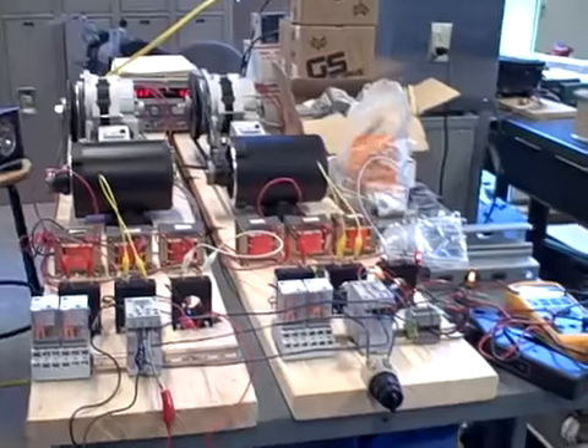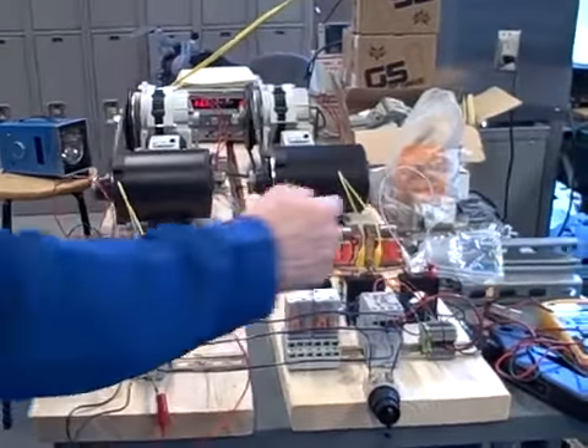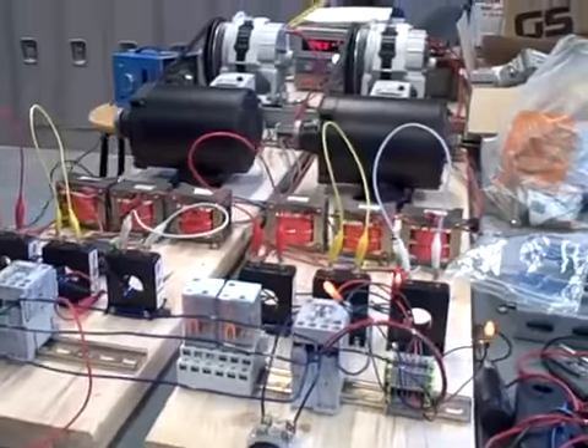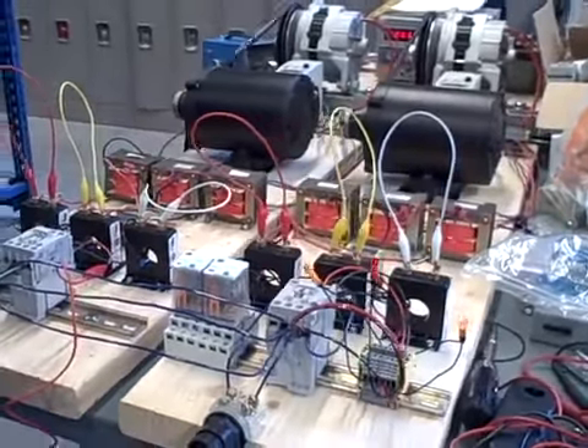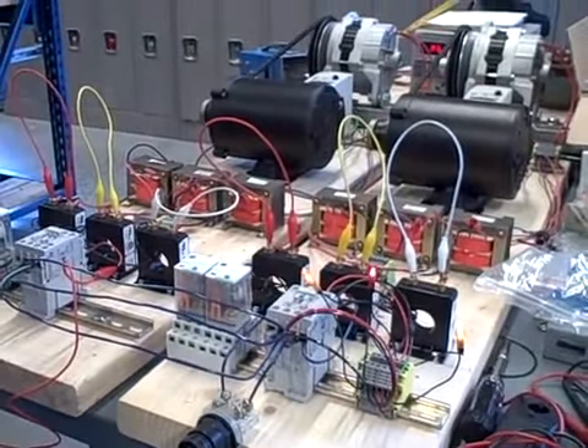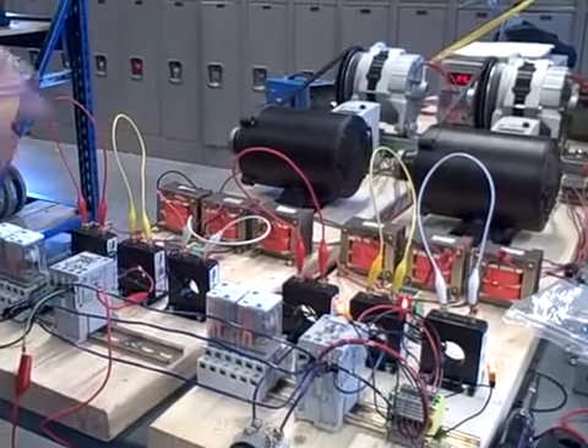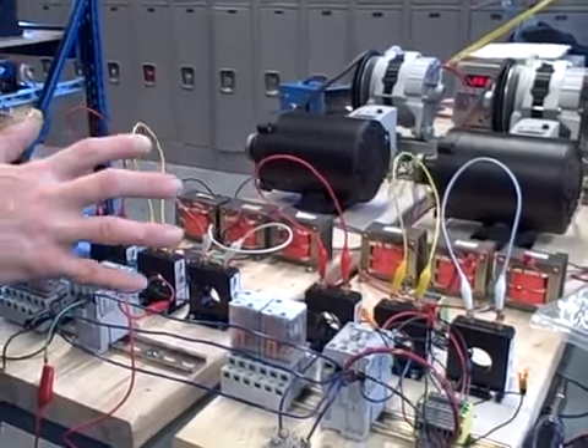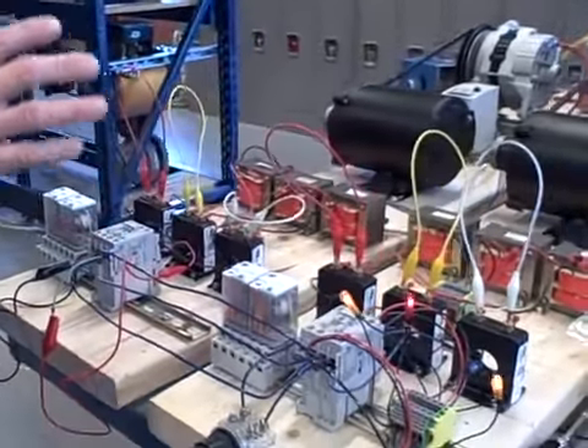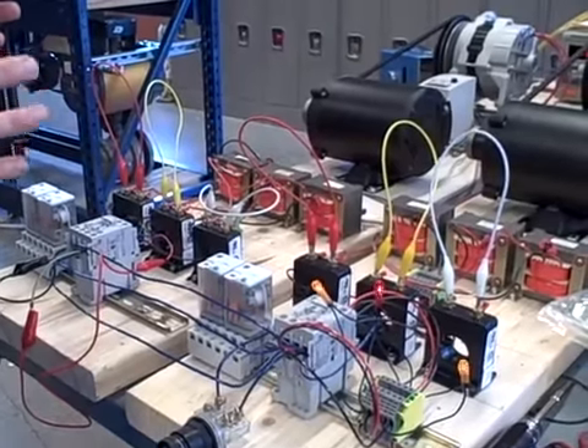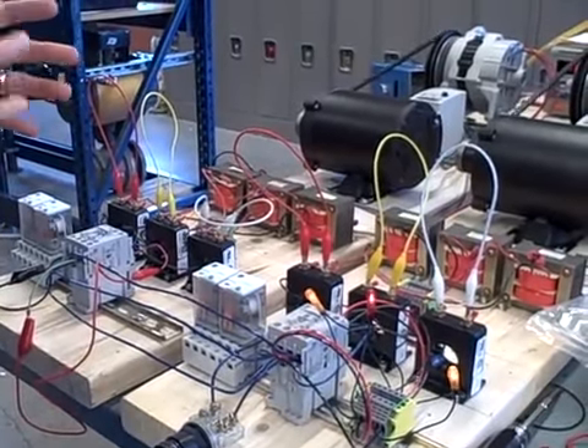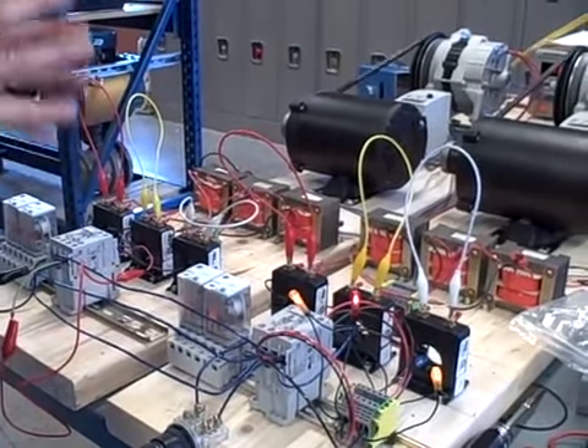That circuit breaker is currently open, and we have three neon light bulbs connected across the poles of each circuit breaker contact. And you'll see these light bulbs are blinking. What that's telling us is that these two generators are not in phase with each other. They're both putting out three-phase power, about the same voltage, but one's going a little bit slower than the other one is.